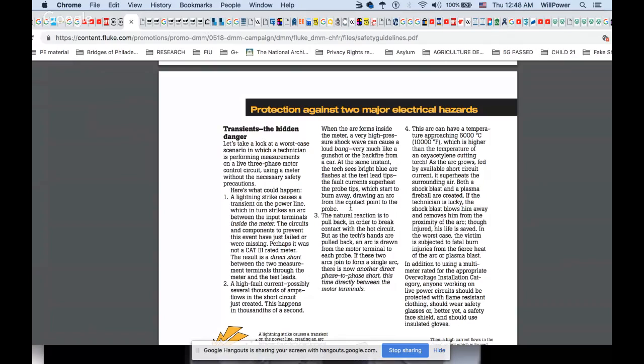This is the one that blows off electricians' arms. You can Google electricians that lost their arms, electricians that lost from the elbow down. How do they do that? Did the nerves die? Some of them do, but some of them, it just blows it off. This is literally an explosion, and it happened because they're using the wrong testers and they're shorting out. The natural reaction is to pull back in order to break the contact with the hot circuit. But as the technician's hands are pulled back, an arc is drawn from the motor terminal to each probe. If these two arcs join to form a single arc, there is now another and direct phase-to-phase short, this time directly between the motor terminals.